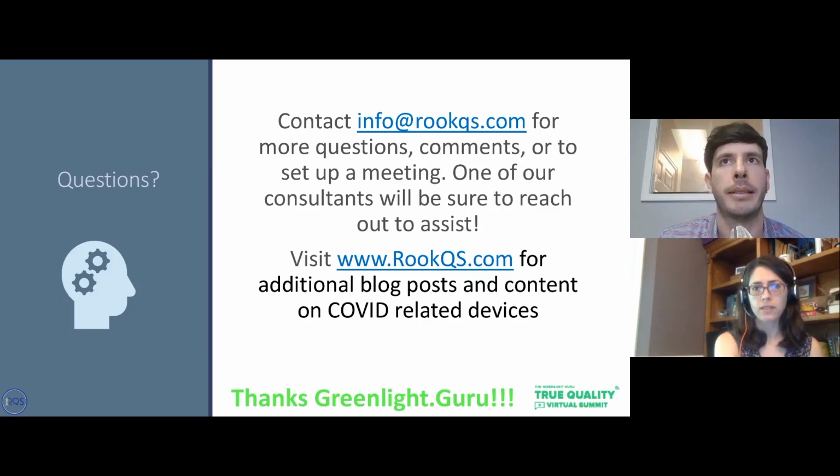I think it depends on the type of product. We have seen some where they do want UDI, such as diagnostics and things like that, but we have seen some where they're not requiring UDI-related barcodes and having to set up that whole process with a GUDID and all of that. So I would say look at the specific product, look at that guidance to identify whether or not you need a UDI for that specific product.